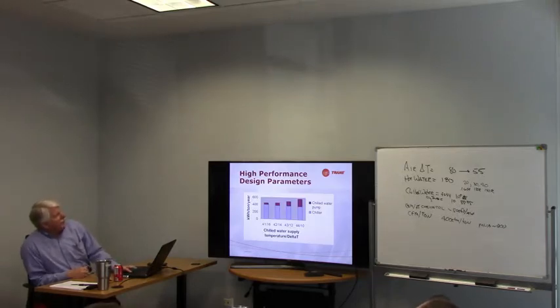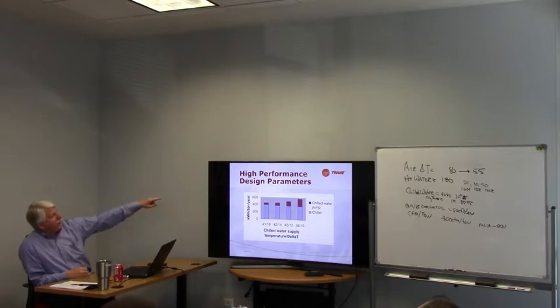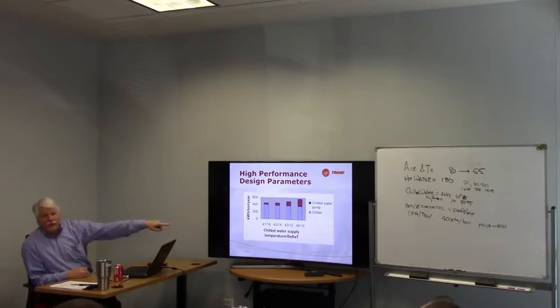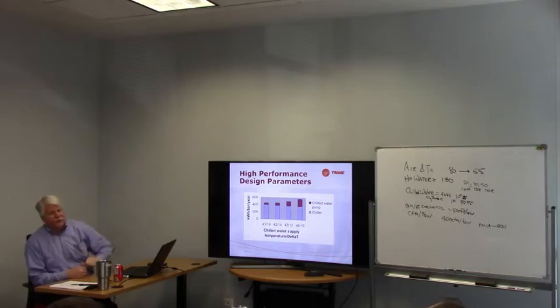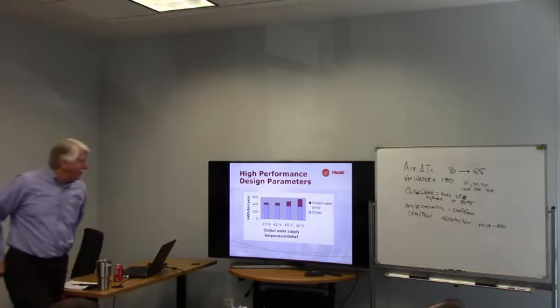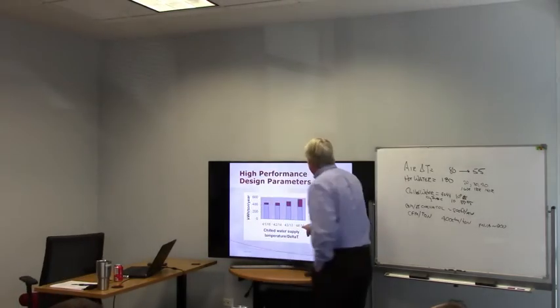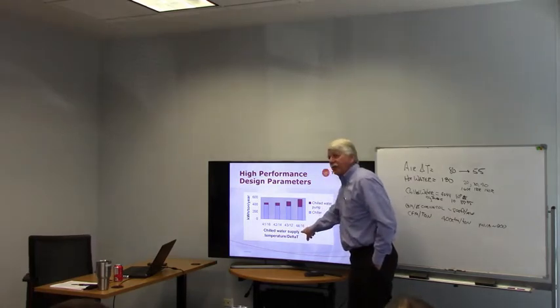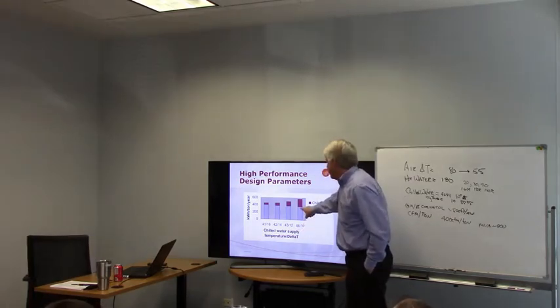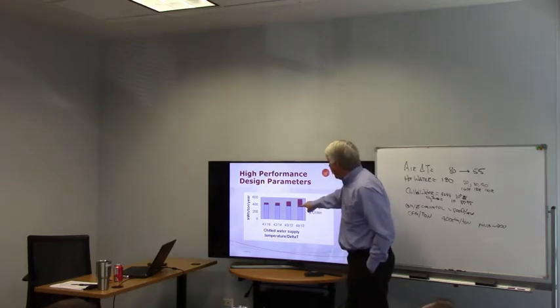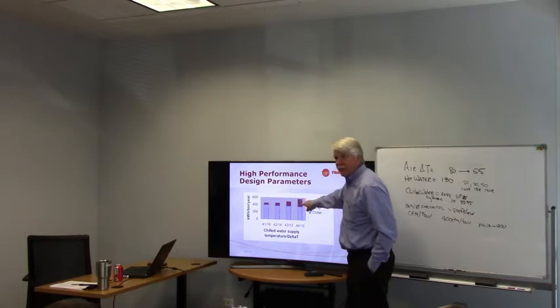Now what we're trying to say here is that if we look at our kW per ton per year at 4 different leaving chilled water temperatures and 4 different delta T's, you can see what our energy is. Okay? Now we said our rule of thumb was 44 degree leaving water and a 10 degree delta T. You can see that the compressor energy is pretty good here. The chiller energy is pretty good. But our pump energy is real big.